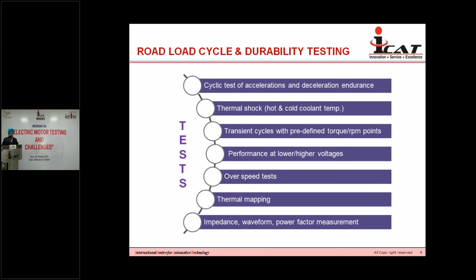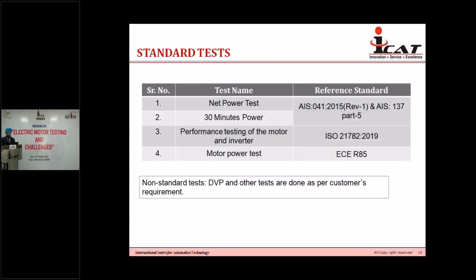We can do thermal shock testing with coolant temperature from 10 to 110 degrees Celsius, transient cycles with predefined torque and RPM points, performance at lower and higher voltages, overspeed tests, thermal mapping, impedance, waveform, and power factor measurement. These are standard tests conducted under regulations, including the net power test and 30-minute power test under AIS 041 and AIS 137 Part 5.